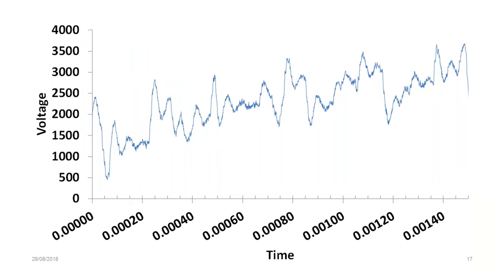So there again is something that we sampled. You can't get this kind of resolution on a typical power quality analyzer. Instead, we use oscilloscopes and capture this sort of data. And what we can actually see here is the rise and fall as the IGBTs fire. And in the very first case, hopefully you guys can see my mouse, but if not, I'll go ahead and highlight this for you.